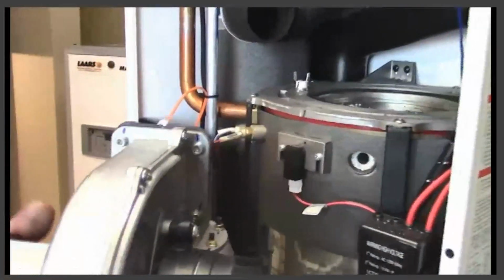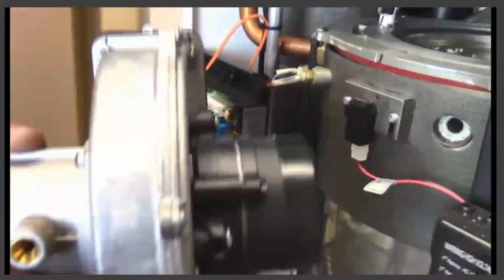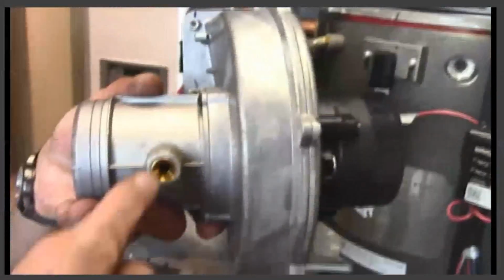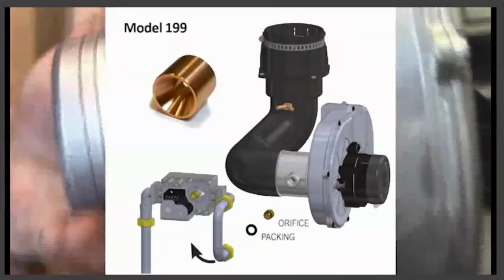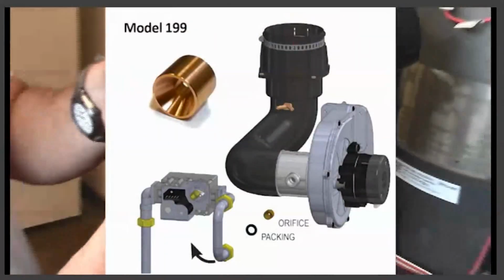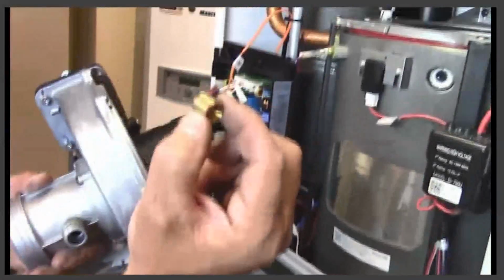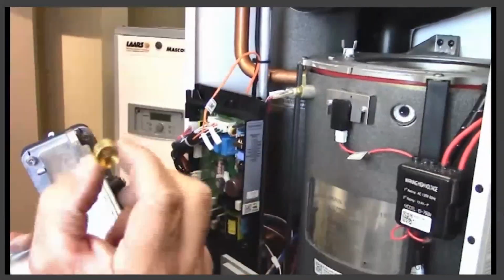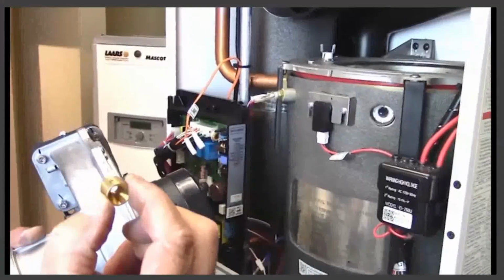During removal of the blower in one piece, you will notice that brass orifice. That is your gas orifice. That orifice can come out very easily. Be careful that it doesn't fall onto the floor. You do need that back in place during reassembly.